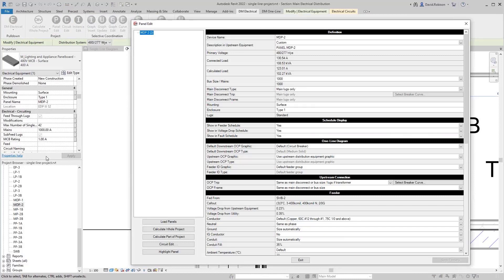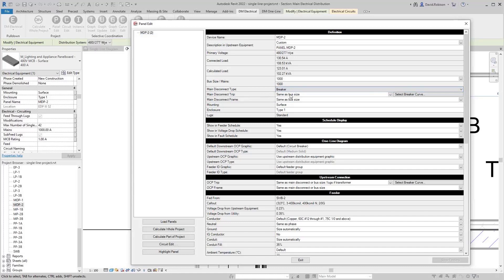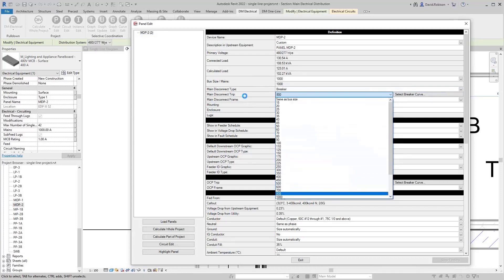For the disconnect, Revit has an MCB rating which we throw out and don't use — they have their mains and MCB rating completely backwards in implementation, so we use our own. You can set the disconnect type as main lugs only, a breaker, or a fused switch. If you choose a breaker or fused switch, you can specify the trip and frame size. It defaults to the bus size, but you can put in a smaller breaker, such as an 800 amp breaker on a 1000 amp panel.